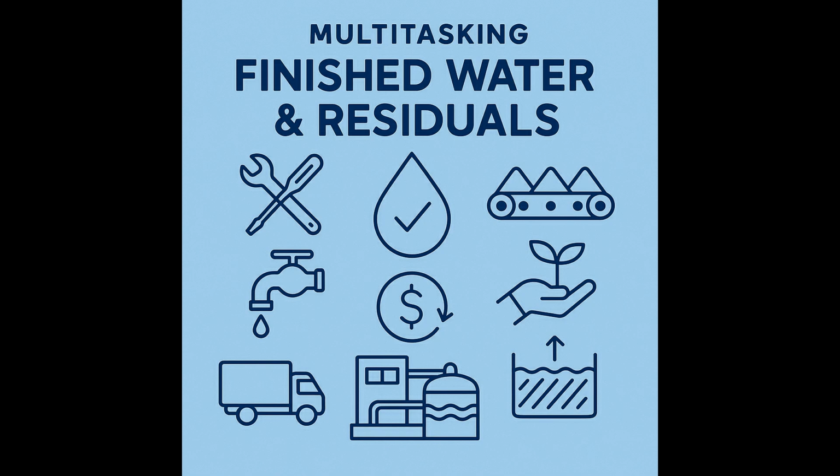Plants need properly sized day tanks, make down tanks, and mixing tanks, usually made of corrosion-resistant materials like plastic or stainless steel, to ensure they don't run out and that the polymer is prepared correctly. How do operators figure out the right polymer and the right dose? Is it just trial and error?